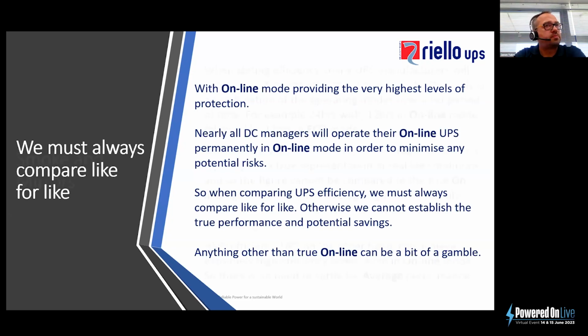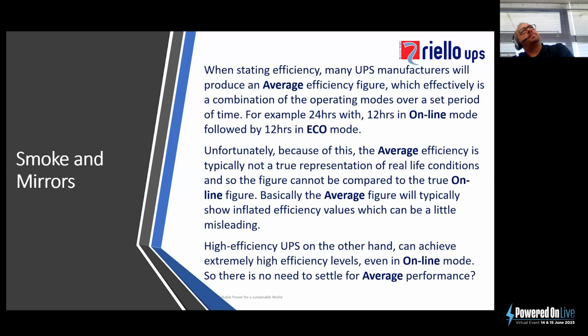Now, in my view, anything other than true online can be a bit of a gamble in terms of power protection. When stating efficiency, many UPS manufacturers will produce what is referred to as an average efficiency figure, which is effectively a combination of operating modes over a set period of time. So, for example, over a 24-hour period, for 12 hours of the day, the UPS system could be in online mode, and for the remaining 12 hours a day, the system could be sitting in eco mode. Obviously, for certain applications, this is perfectly acceptable, but for 24/7 data centers, this is generally not accepted because you are at some point exposing the data centers to higher levels of risk. Unfortunately, because of this, the average efficiency typically is not a true representation of the real life conditions, and so the figure cannot be compared to the true online figure.